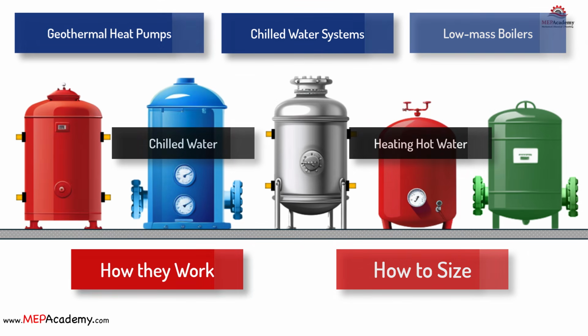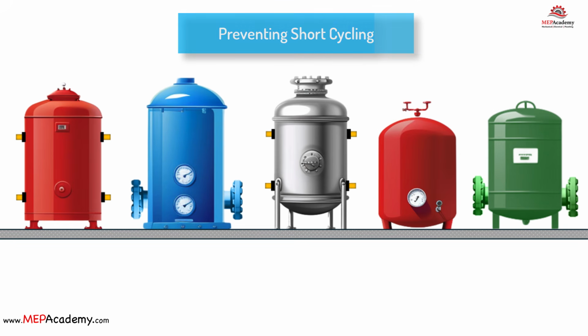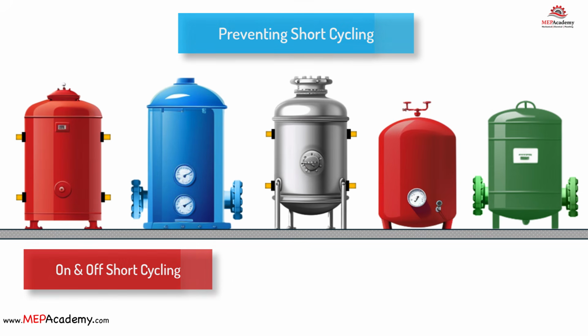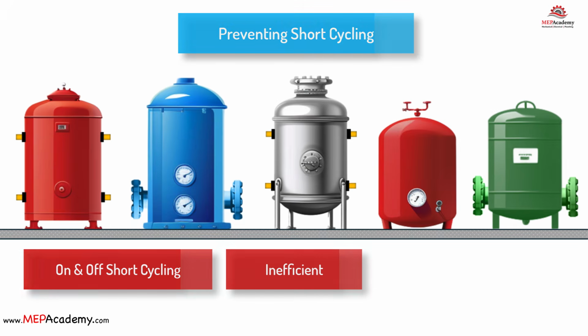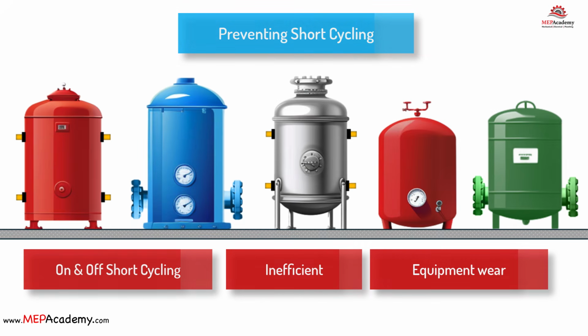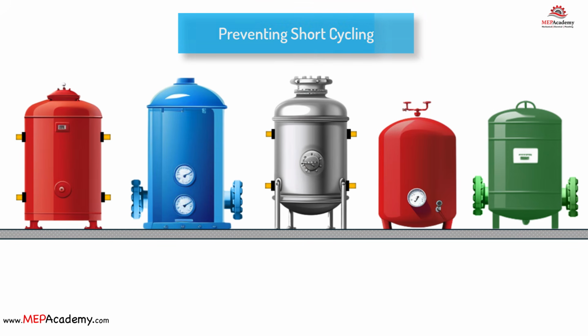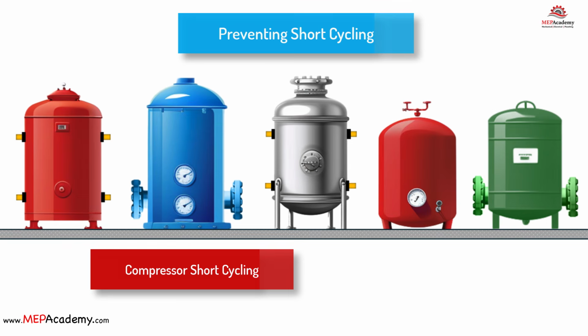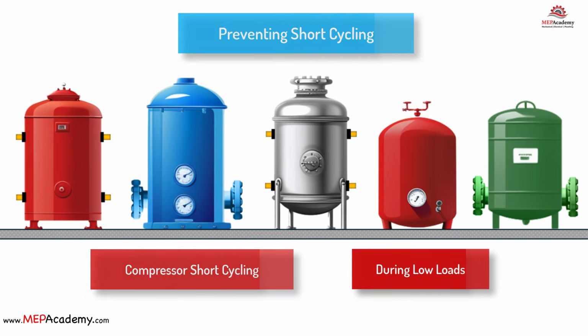A buffer tank serves several important functions. Preventing short cycling. Buffer tanks prevent short cycling of boilers, heat sources, and chilled water systems. Short cycling occurs when the heating or cooling system turns on and off rapidly due to small fluctuations in demand. This can be inefficient and cause wear and tear on the heating and cooling equipment and is one of the top causes of failure in a heating system. The buffer tank provides a reservoir of heated water, allowing the system to operate more steadily. A buffer tank can help prevent a compressor from short cycling during low loads in a geothermal or chilled water system.